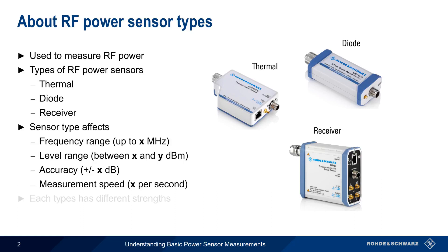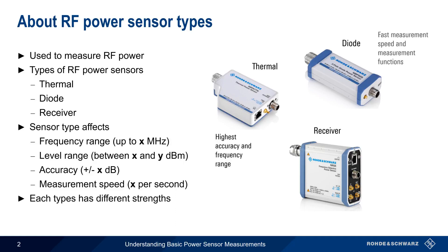Each power sensor type has different strengths or weaknesses. For example, we find the highest accuracy in thermal sensors, fast speed and many statistics and measurement functions in diode sensors, and very wide level range and frequency selectivity in receiver-based sensors.